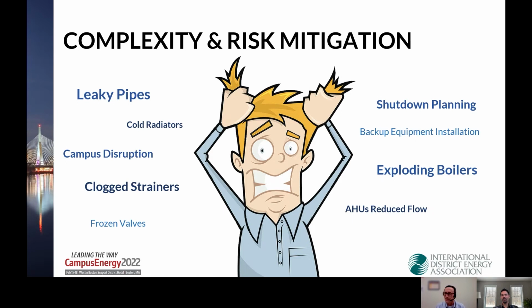You get new boilers, you get new pipes, you get new air handlers. And this was a very innovative way to get a lot of new, but also reuse a lot of existing infrastructure. So we did have some concerns. We're talking about reusing steam and condensate piping, some of which has been out of service for 40 years. We're talking about converting three 80,000-pound steam boilers that are over 50 years old.